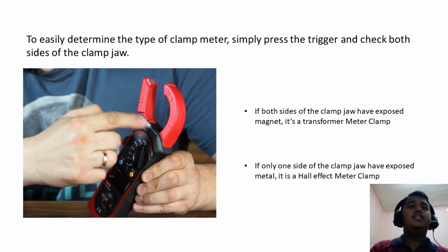To easily determine the type of clamp meter you are using, simply press the trigger and check both sides of the clamp jaw. If both sides of the clamp jaw have exposed magnet, it's a transformer clamp meter. If only one side has exposed metal, it is a Hall effect clamp meter.